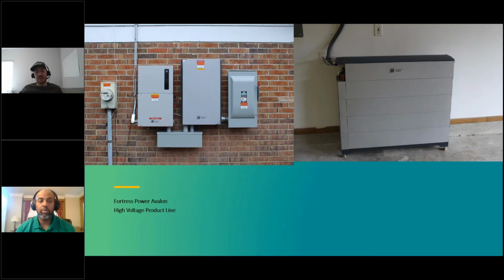If they had AC coupled instead, most AC coupling gives you about 85% efficiency, which means in that AC coupled option, to get the exact same amount of energy, they'd have to expand the PV size by 10%, and that starts to add up. In that AC coupling situation they'd only get 85 kilowatt hours with the exact same system, because every time we convert energy, we lose energy. On the DC side, it gives us that extra boost, that extra efficiency.